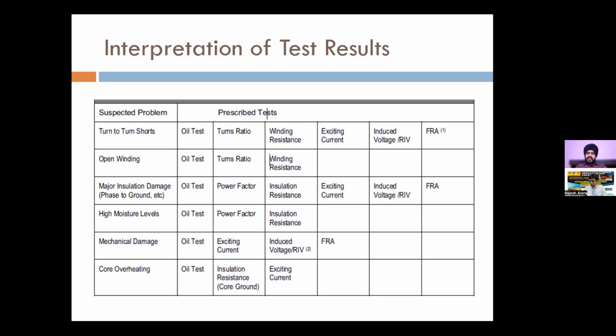If there is insulation damage, then insulation resistance, excitation current, and FRA will indicate some problem. If the moisture levels are high, then the oil test results will also indicate some problem, and the IR value will also deteriorate. If there is any mechanical damage inside, like I said, due to short circuit forces, then excitation current and induced voltage, and most importantly, our FRA test will be quite helpful in identifying this issue.